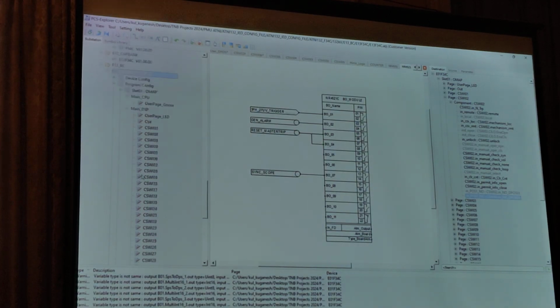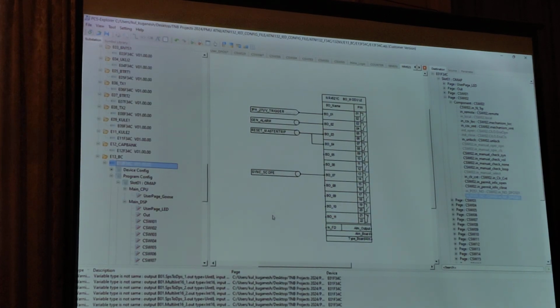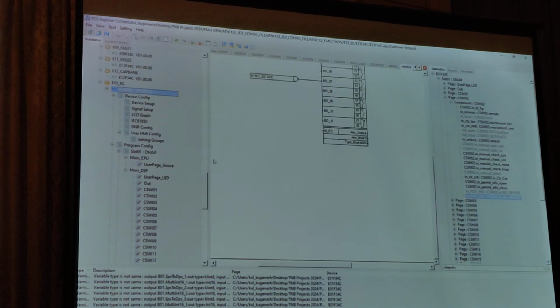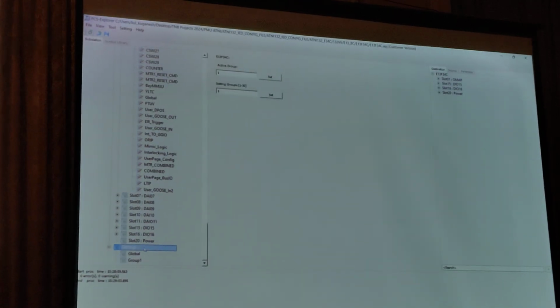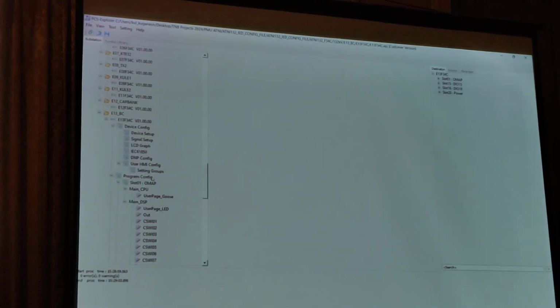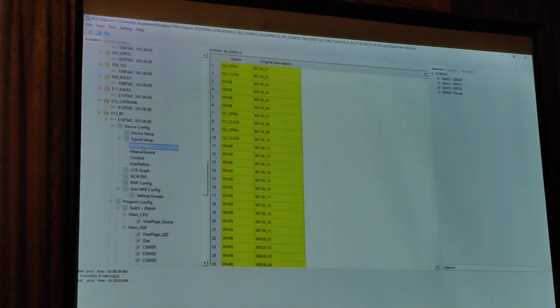Okay, so just like you asked a question, right, where if you have an extension BCU, what are the main things that you want to concern about changing? Okay, so I will tell you. Okay, first of all, you need to ensure what typical is that. Bus coupler, bus section, OHL, UGC, OTX, OSGT. Okay, once you ensure the typical, then you already got the DEV file. First thing you need to check is signals.